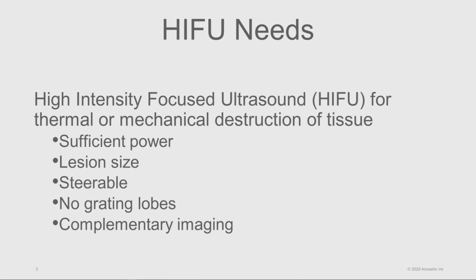To truly realize the promise of HIFU, the ultrasound transducer needs to meet certain requirements. First of all, there needs to be sufficient power output, either continuous for thermal or instantaneous for mechanical, to ensure that the treatment can be performed quickly and that the depth of penetration is sufficient for the task. This points us to a large area, high power, actively cooled transducer.